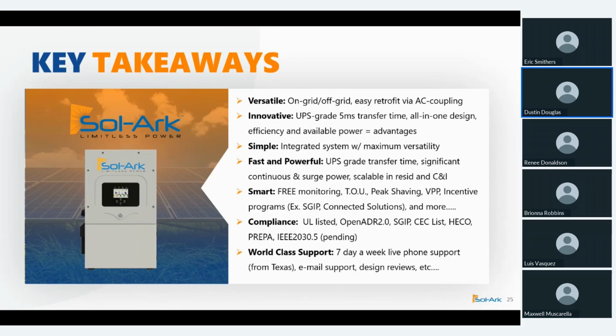In that specific scenario, yes, you can have the AC coupled inverter on the gen input. You could have an external transfer switch to go between the grid and the generator to land on the grid input. On top of that, we're working with a fuel cell company to have a way for that DC power to land into our MPPTs. And for the wind turbine, you could use an external charge controller with a dump load connected directly to the batteries, getting all those power sources into one configuration.